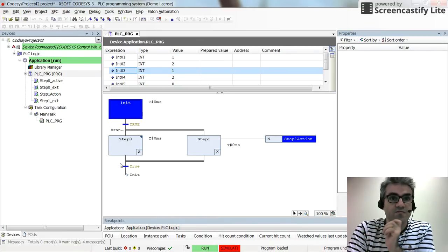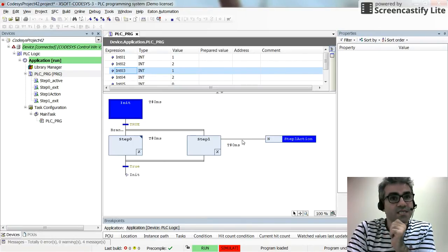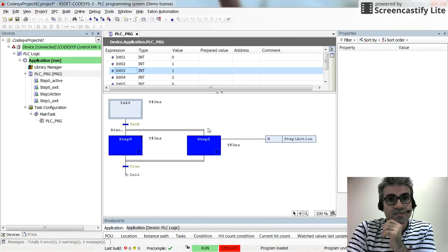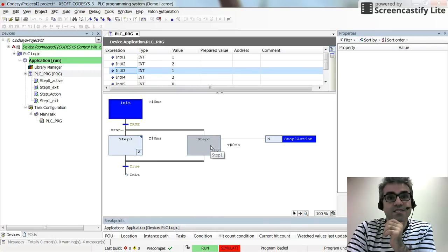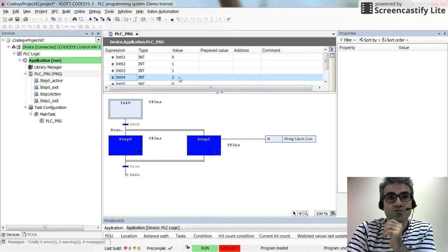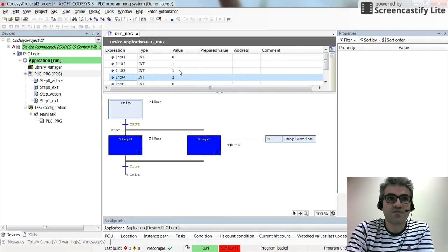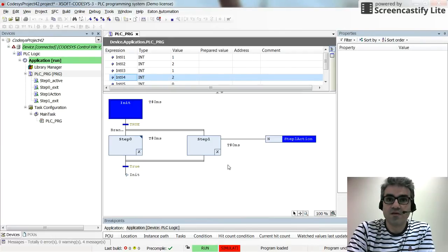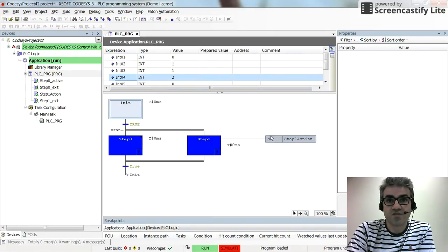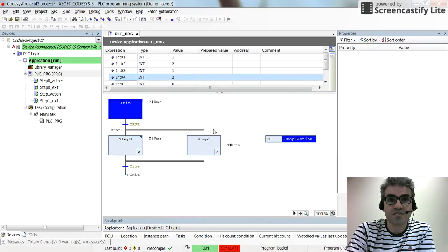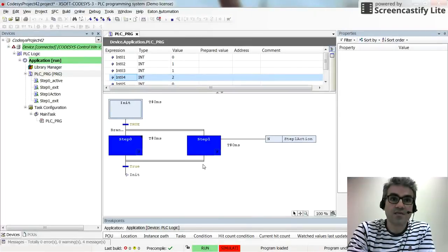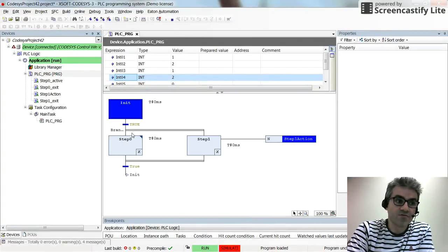It's executed only once — when the execution enters Step 0, it executes once and that's it. But for Step 1, the IEC conforming action with qualifier N is executed twice: once when we enter the step and a second time when we exit the step. That's why the value for int04 is equal to 2, because the addition is performed two times. So the IEC conforming action with qualifier N is performed at least twice — once on entry and once on exit — while the step active action is executed only once.